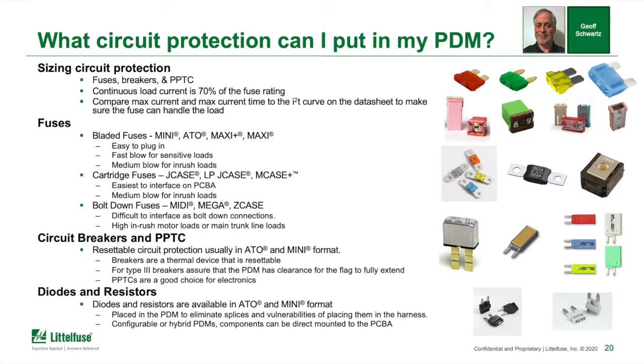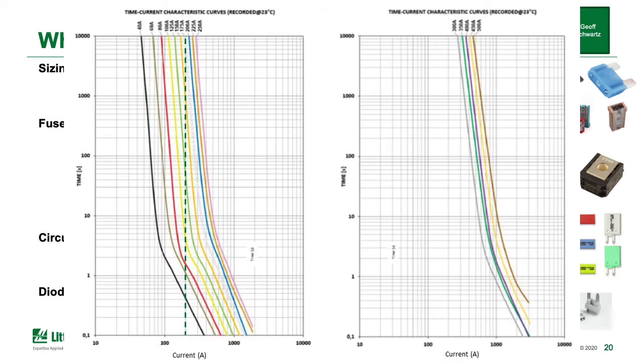In addition to the continuous current, you should compare the max current and the max current time to the I²T curve on the data sheet to make sure you can handle the fused load. So this is your I²T curve. And let's assume we have our 150 amp fuse, which is the orange line on there, and we put a 200 amp load on it as the max current. As you can see, as long as that 200 amp load lasts for less than about 700 seconds, that fuse will be all right. So you don't need to worry about it, and you've checked your max current and your max current time.